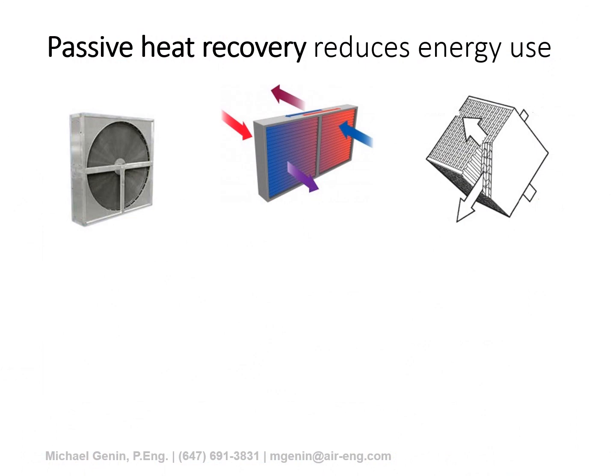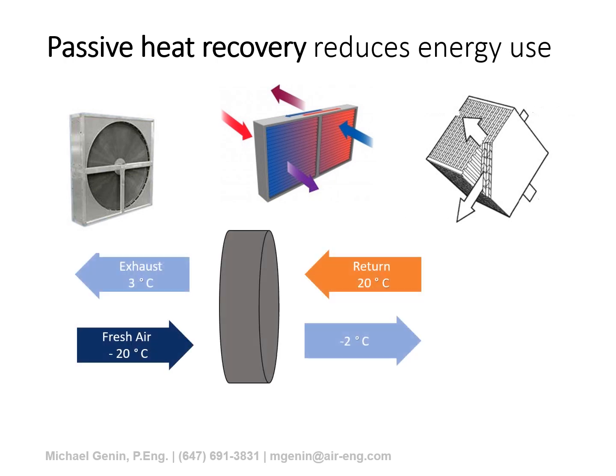So first we're going to talk about the heat recovery opportunities that exist on the ventilation side, or the air-to-air side. And many of us will be familiar with what I will call passive heat recovery devices. These might be heat wheels, heat plates, or heat pipes. And that's where the air is brought over an area that's in close proximity, so we can exchange heat energy between your supply and exhaust air streams. And here's an example where we're bringing fresh air of -20 over a heat rotor and partially heating it up with some return air that's brought back at room temperature, or 20 degrees. And in these examples, you're going to need some kind of top-up heat energy, where we still have to typically burn fossil fuels to bring that remaining amount of air back up to a room neutral condition, or room temperature condition.